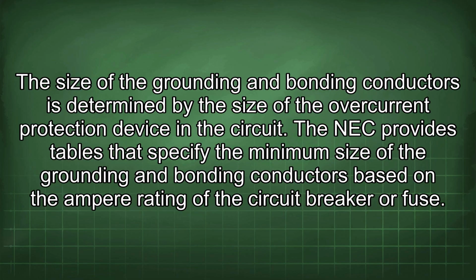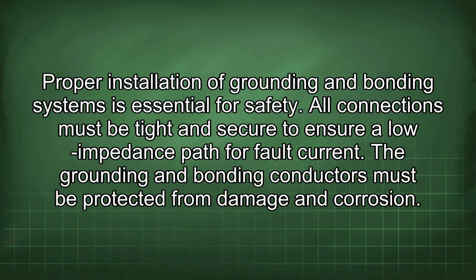The size of the grounding and bonding conductors is determined by the size of the overcurrent protection device in the circuit. The NEC provides tables that specify the minimum size of the grounding and bonding conductors based on the ampere rating of the circuit breaker or fuse. Proper installation of grounding and bonding systems is essential for safety. All connections must be tight and secure to ensure a low impedance path for fault current.